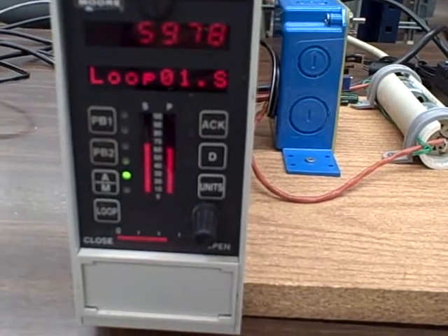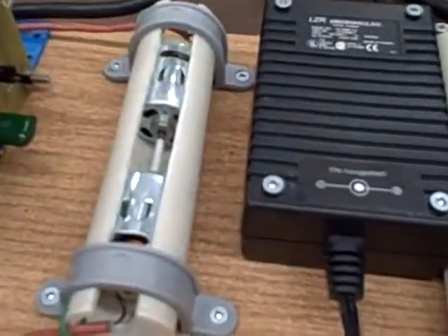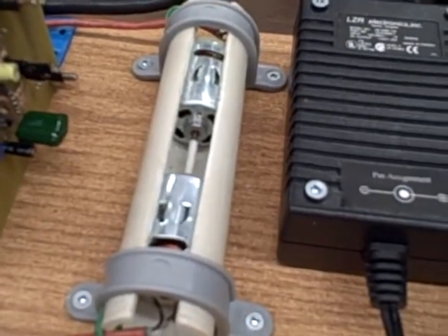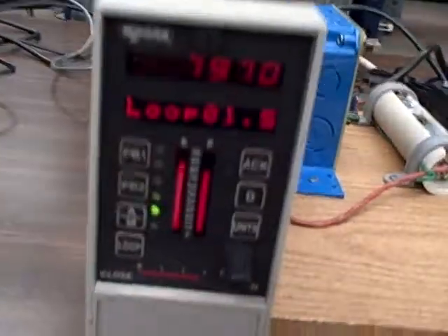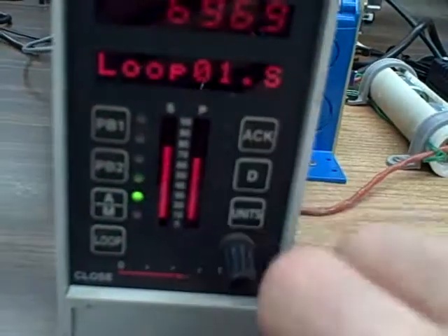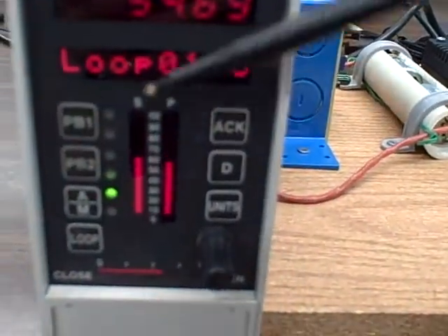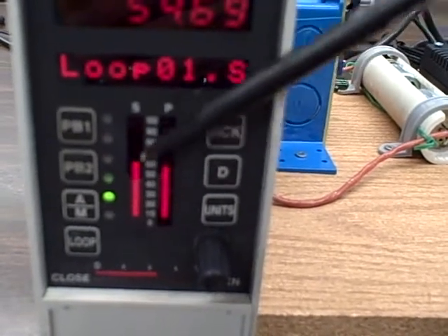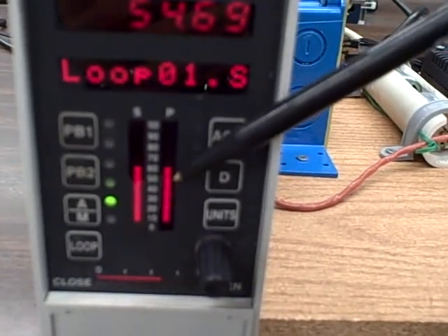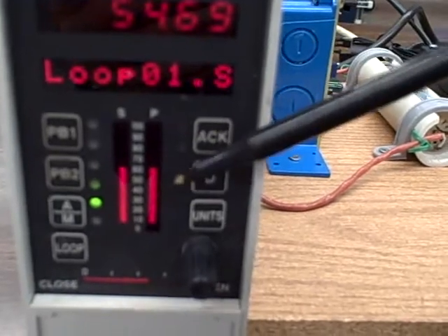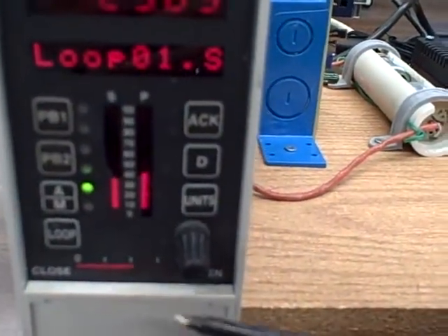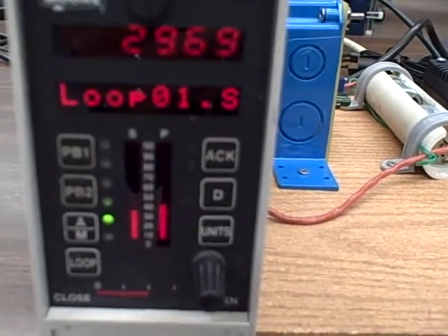You can even hear the motor oscillate. I'll put the camera closer to the motor and you can hear it again. You can see the oscillation in the bar graph when I go up and when I go down. In automatic mode, I make a set point change, which makes the set point bar graph rise or fall. The process variable bar graph then oscillates afterwards, and the output oscillates as well as the controller attempts to stabilize the process variable at set point.